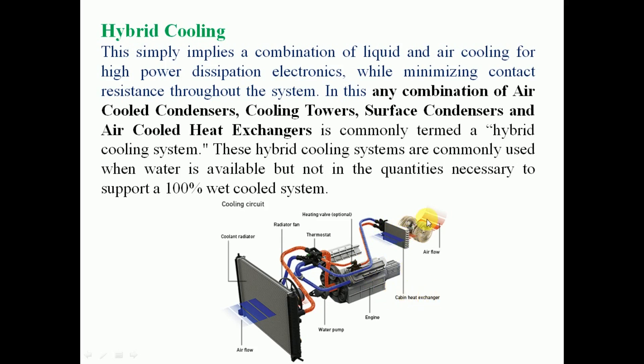In a hybrid cooling example for an electronic device with high heat output, air is blown over the component to carry some heat, and a water-based or oil coolant is also circulated to cool it. The cooled coolant (shown as blue) circulates and gets heated (shown as red), then is circulated to a radiator to exchange heat with the surrounding air. A pump recirculates the coolant back to the cabinet. Both air cooling and liquid cooling are used together — that is hybrid cooling, used for higher heat exchange requiring a combination of heat transfer technologies.